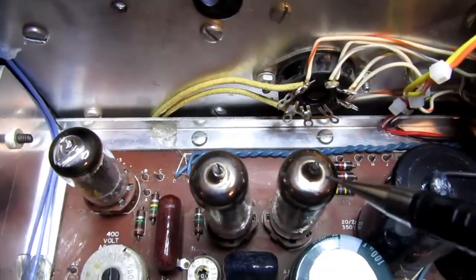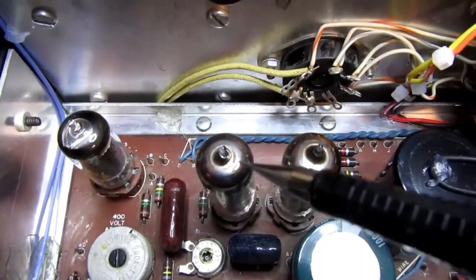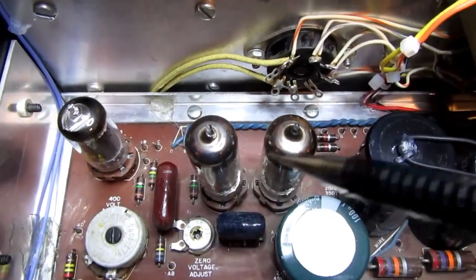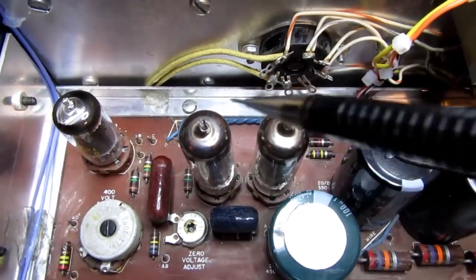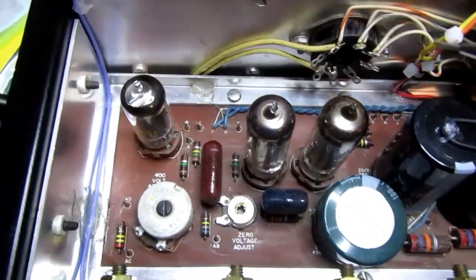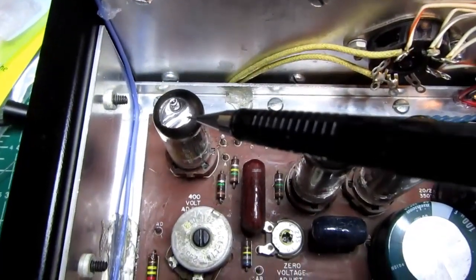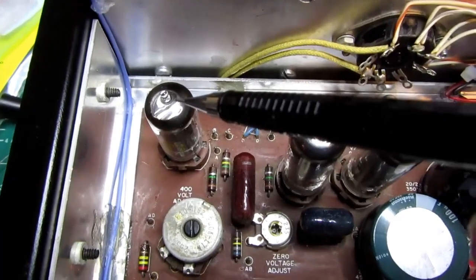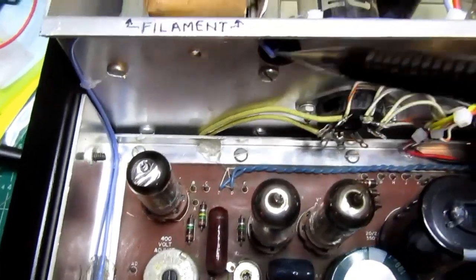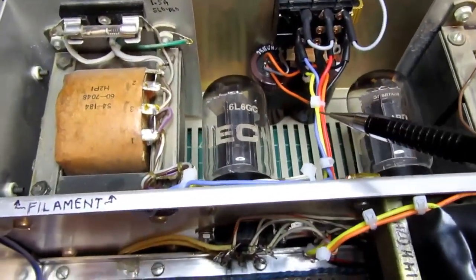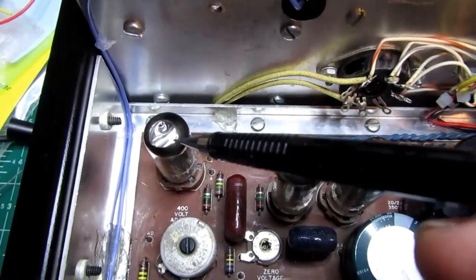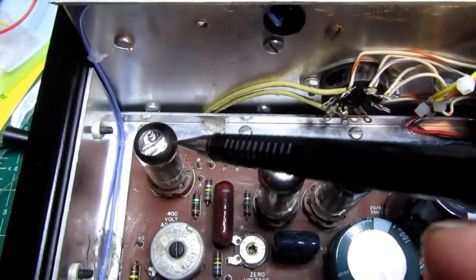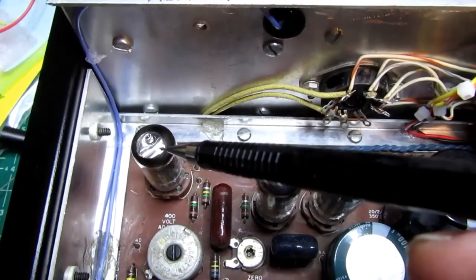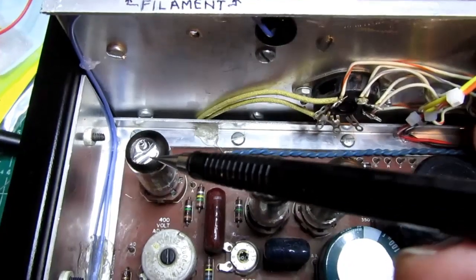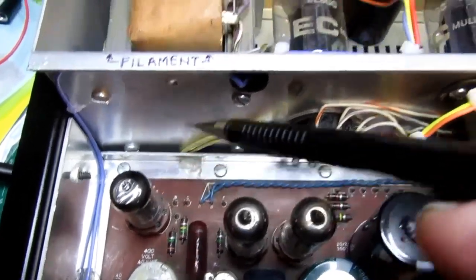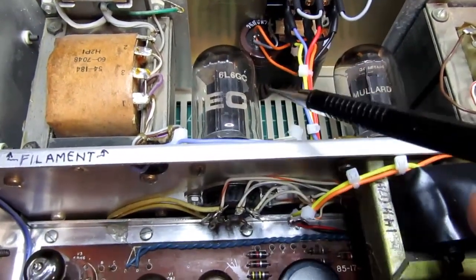These two are voltage regulator tubes. Each one regulates 150 volts across it. So between the two of them, they comprise a 150 volt / 300 volt reference voltage source. This tube here is another pentode tube, and it's being used as the error amplifier for the feedback on the main high voltage supply, the same one that these two tubes work with. So basically this is the one that looks at the reference voltage coming off of here, and it looks at the actual output voltage of the main high voltage B+ power supply. It compares them and decides what kind of a correction signal it should be sending to these two so that they actually do the regulation.